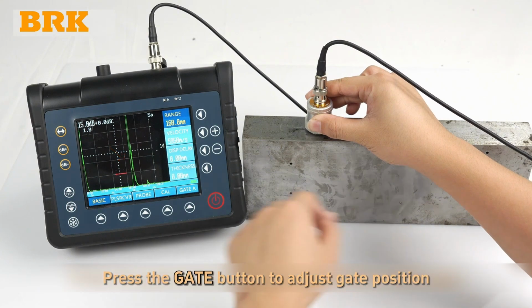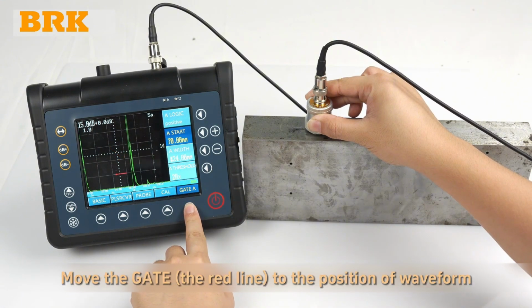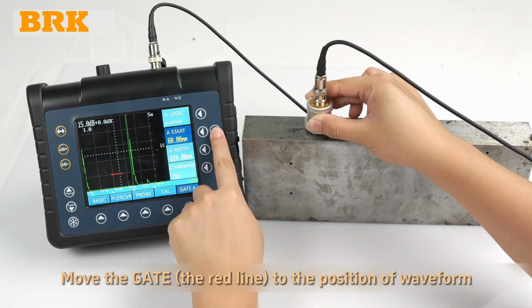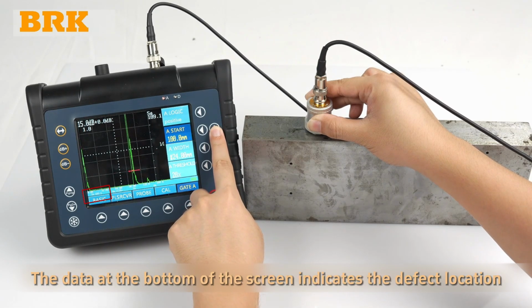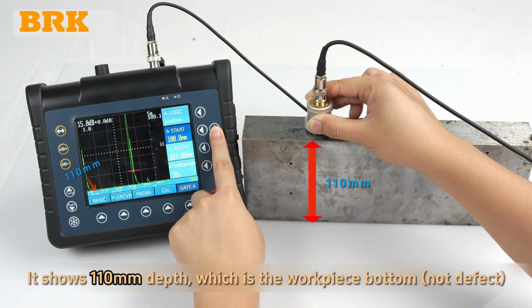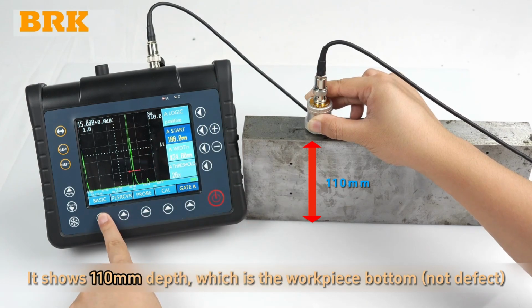Press the gate button to adjust the gate position. Move the gate to the position of waveform. The data at the bottom of the screen indicates the defect location. It shows 110 mm depth, which is the workpiece bottom, not a defect.